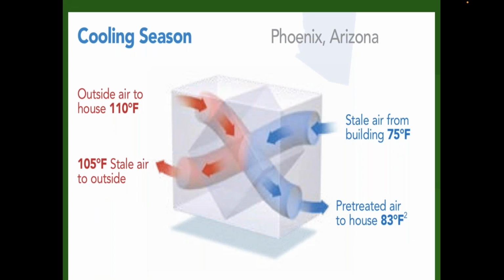But for example, the system I'm putting in my house will have the ability to take outdoor air at 110 degrees, and then it takes the stale air from the building, let's say at 75 degrees, and recovers that energy and brings me preheated air in at 83 degrees, and then it'll exhaust that air at 105. So these systems use very little watt draw, but the beauty of these systems is that they allow you to bring in fresh air and recover the energy that you pay to heat and cool your homes.